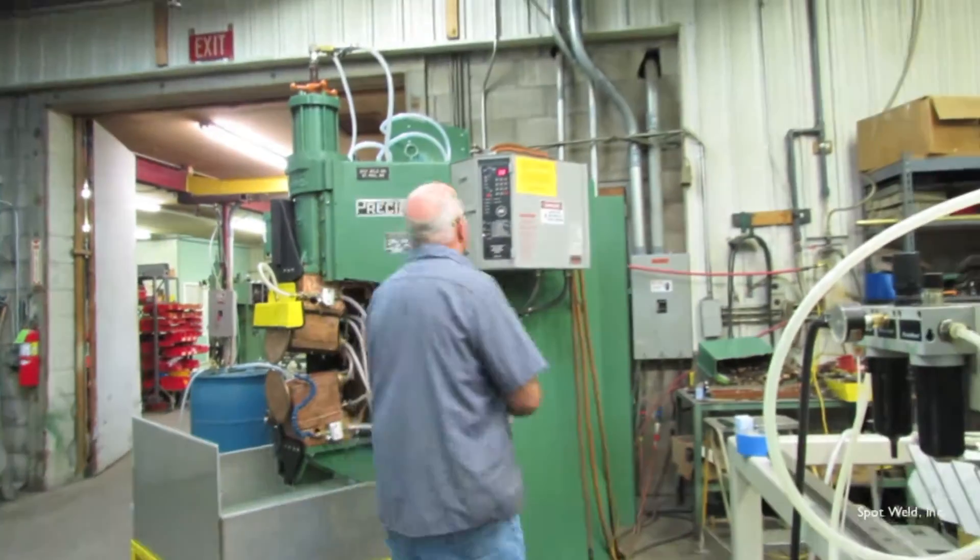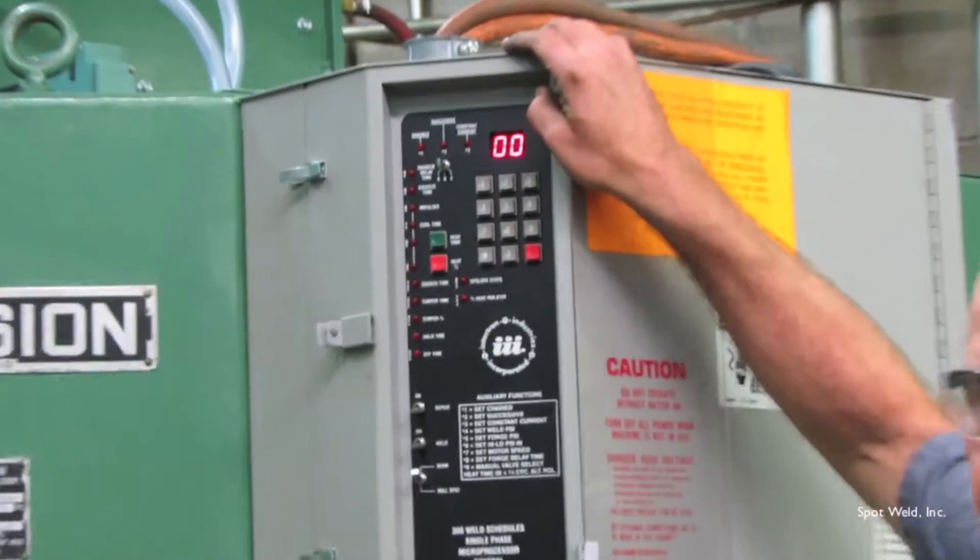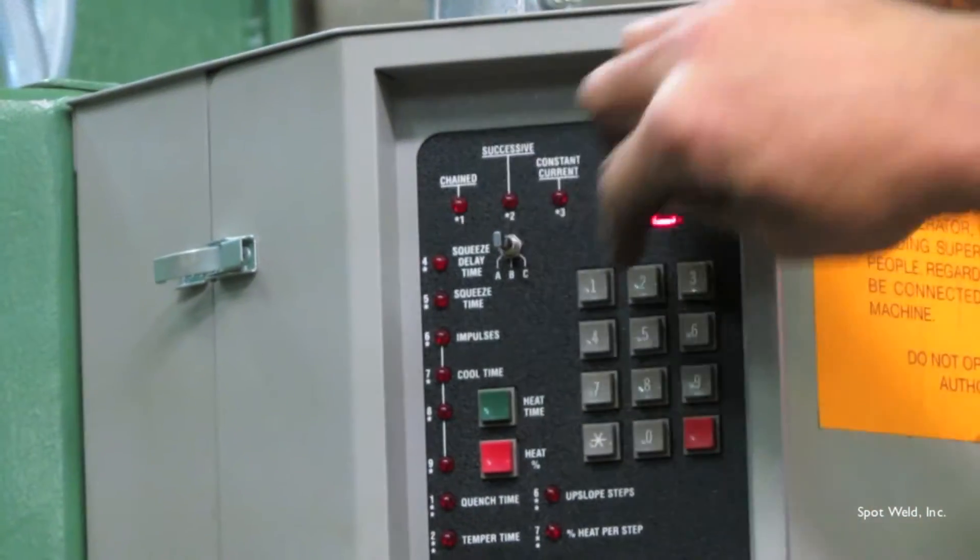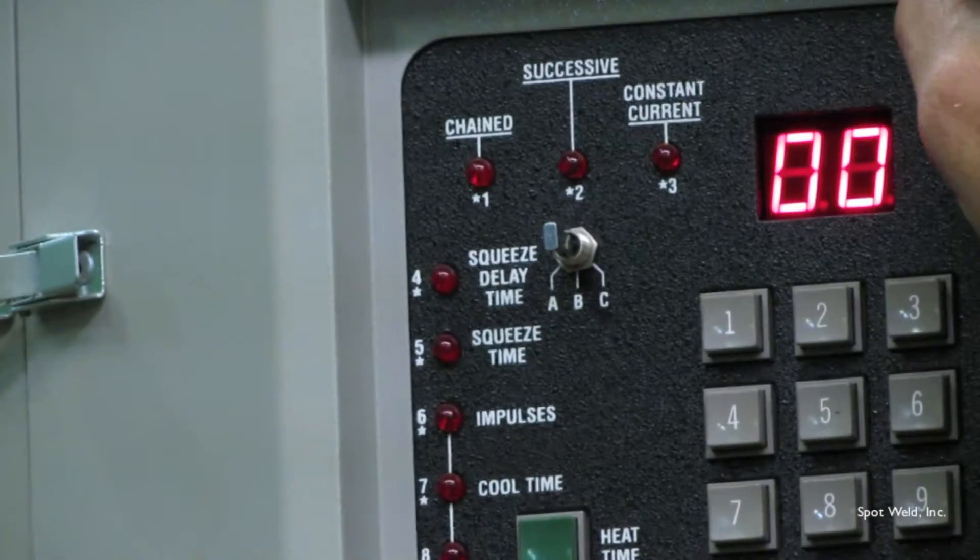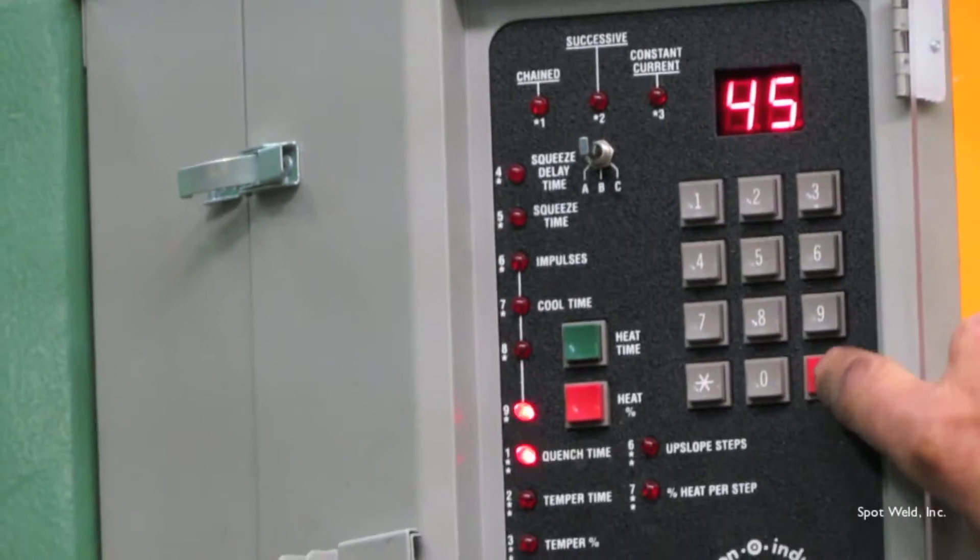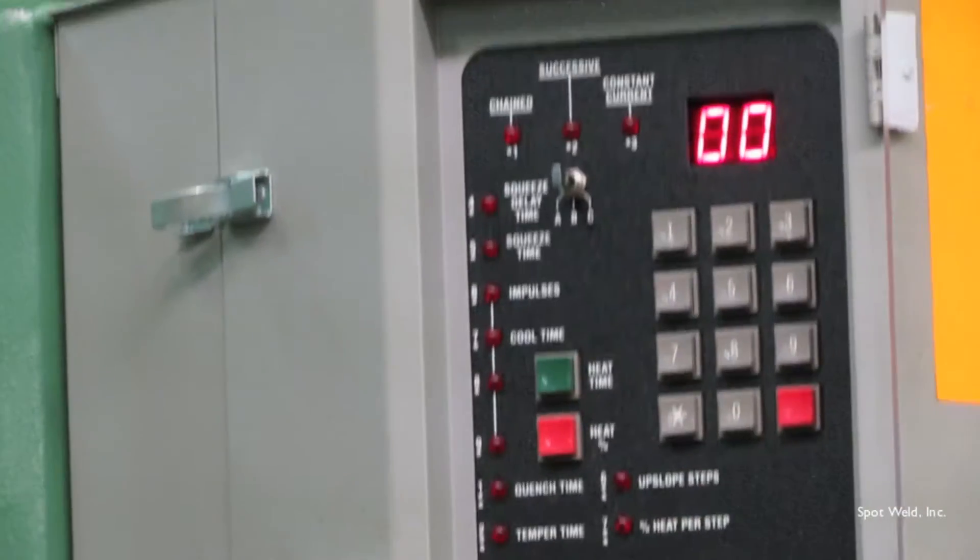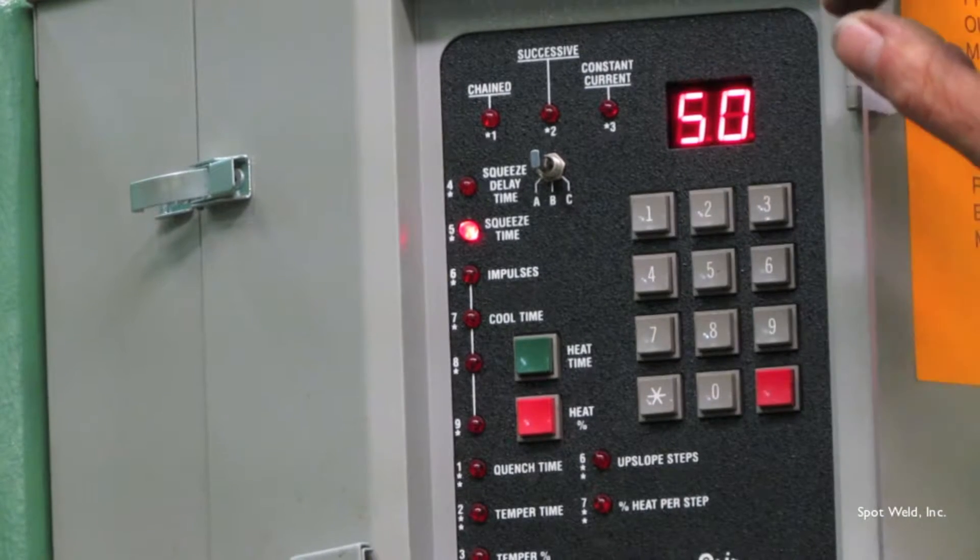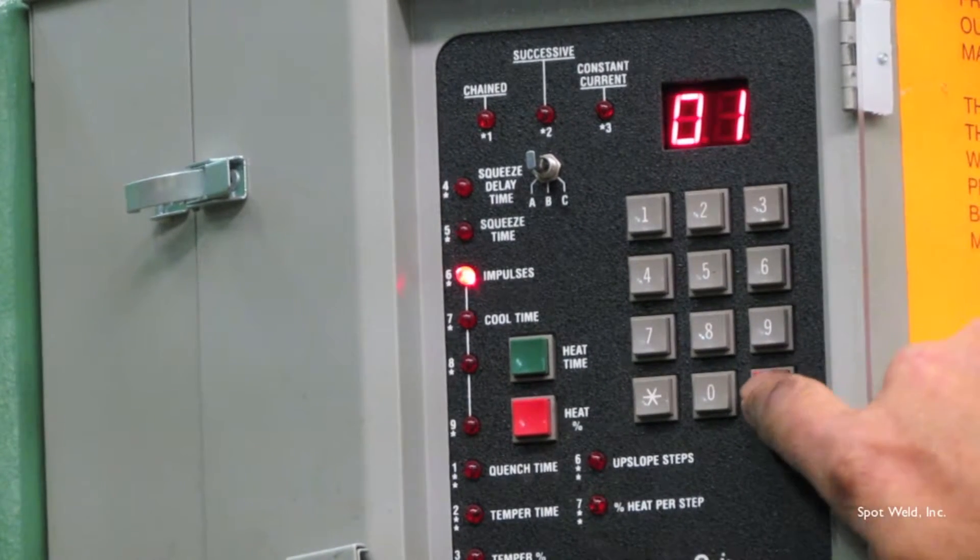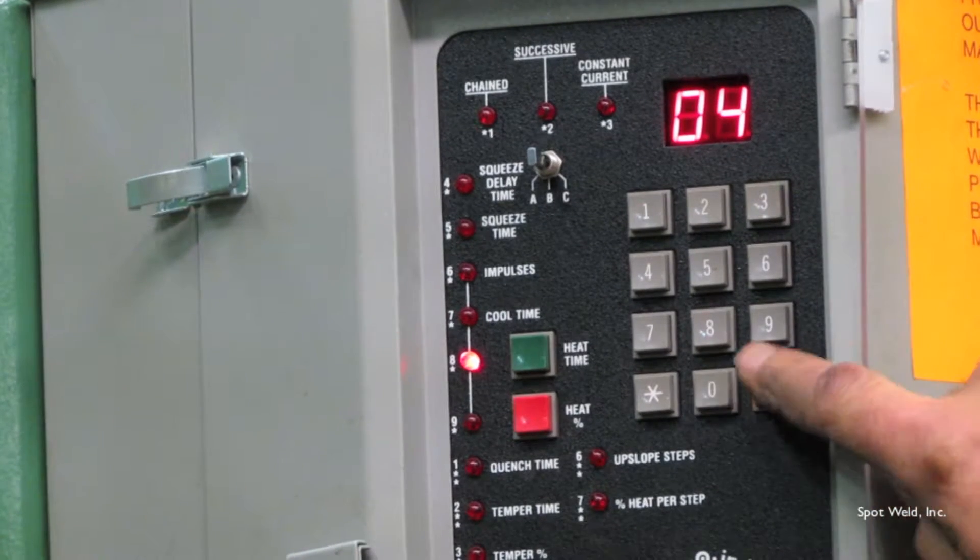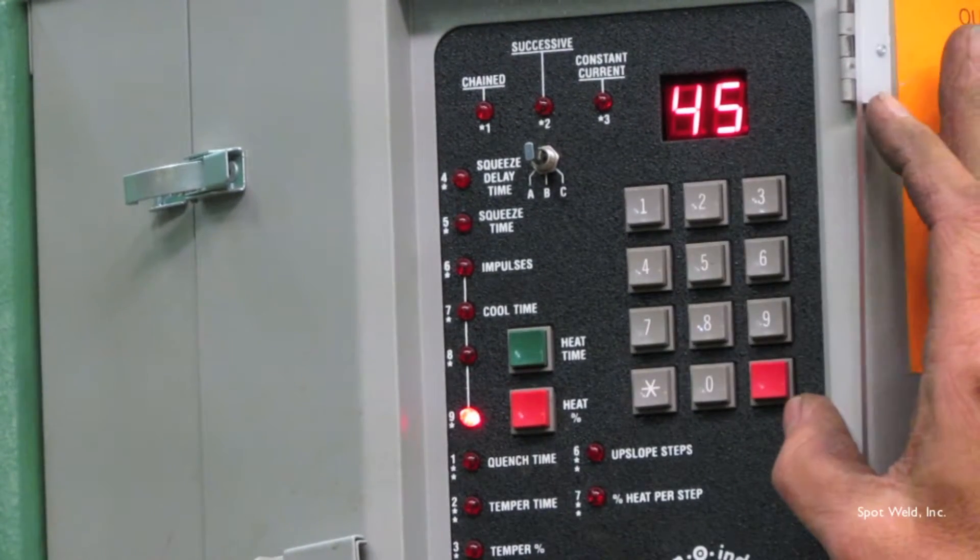Now we're going to dial in a weld schedule. The Entron 108, we have 100 weld schedules in each A, B and C categories on this toggle switch. Right now we're going to work with schedule zero zero. Squeeze of 50 cycles. Any time parameter on this controller is in cycle time. We only need one impulse. Cool time of 2. Heat time of 4. At 45%. And hold time of 15.